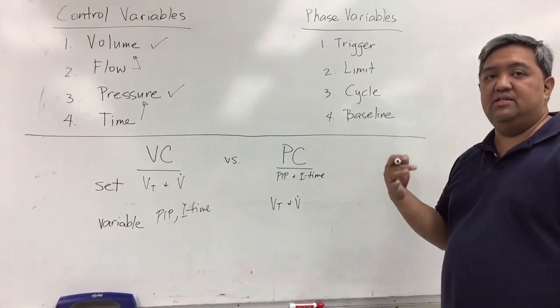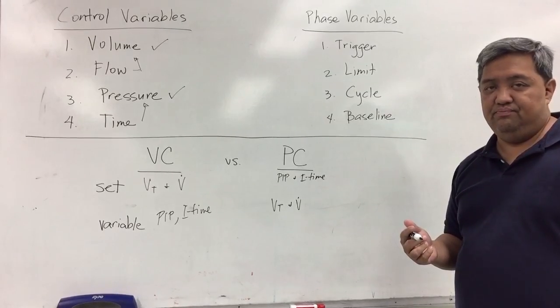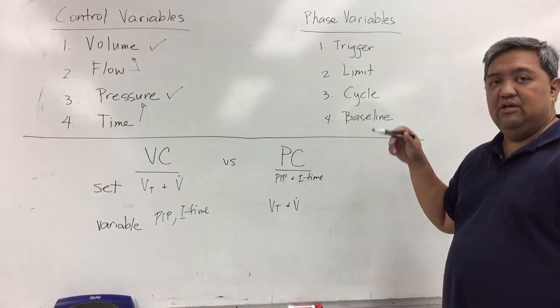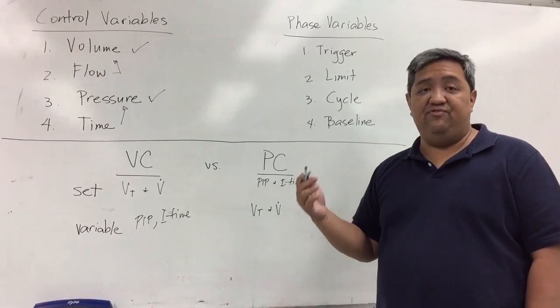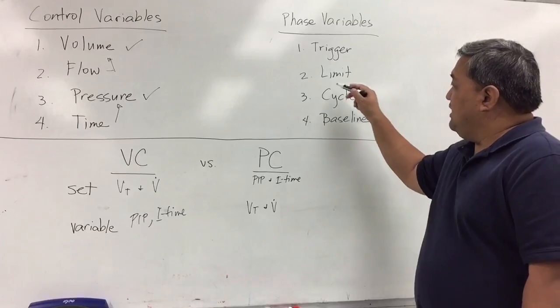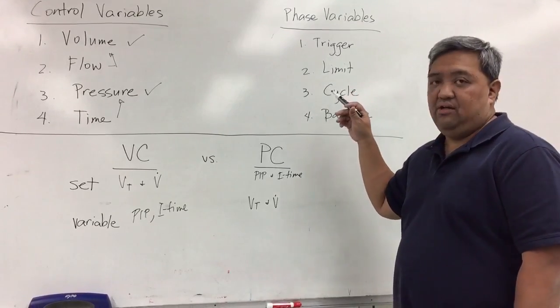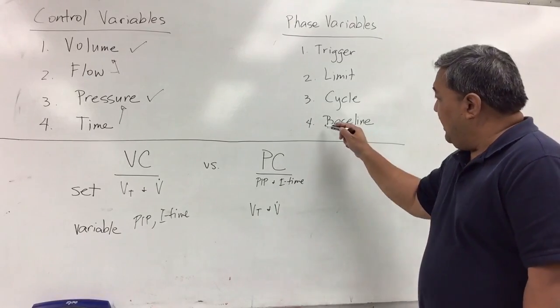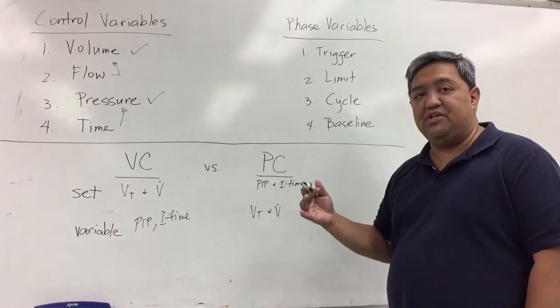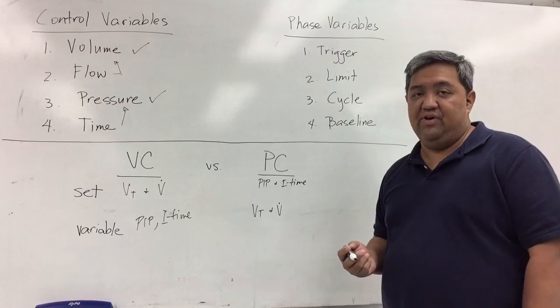Trigger is basically the start of inspiration. Limit, although it does not end inspiration, it sets an upper limit on a given variable. The cycling mechanism, or the cycle, basically ends inspiration and the start of exhalation. And then baseline basically is the pressure at the end of exhalation.